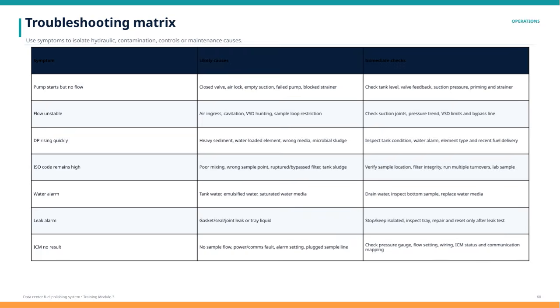Leak alarms generally indicate a gasket, seal, or joint leak, or tray liquid issues. It's crucial to stop or isolate the system, inspect the tray, make repairs, and only reset the alarm after a successful leak test. Finally, if the ICM shows no result, this might be due to no sample flow, power or communication faults, alarm settings, or a plugged sample line. Checking the pressure gauge, flow settings, wiring, ICM status, and communication mapping will help resolve this. This matrix is a valuable tool that helps streamline diagnostics and ensures that operators can respond effectively to maintain optimal system performance.